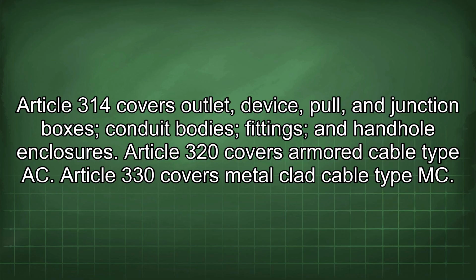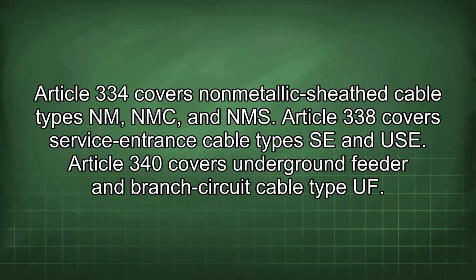Article 314 covers outlet, device, pull, and junction boxes, conduit bodies, fittings, and handhole enclosures. Article 320 covers armored cable type AC. Article 330 covers metal-clad cable type MC. Article 334 covers non-metallic sheathed cable types NM, NMC, and NMS. Article 338 covers service entrance cable types SE and USE.